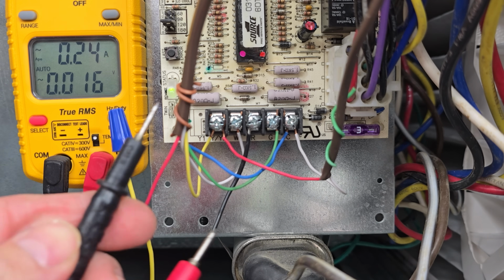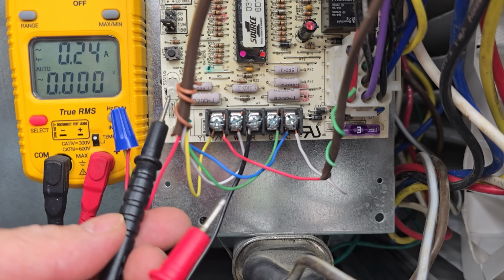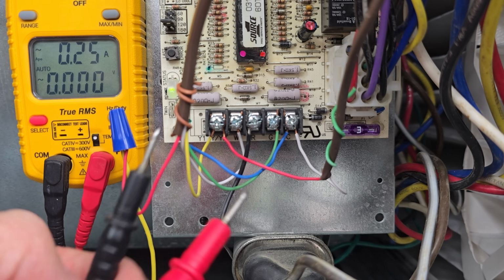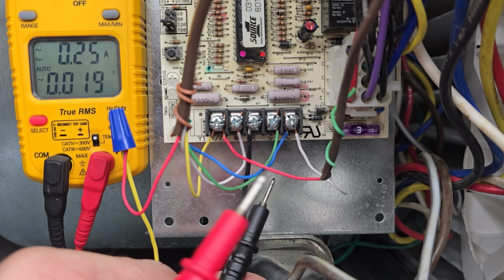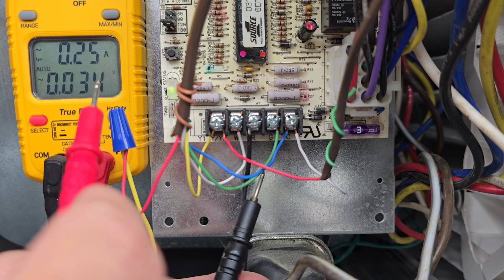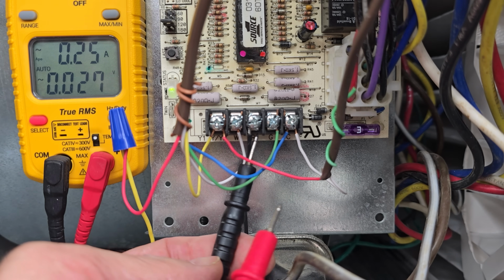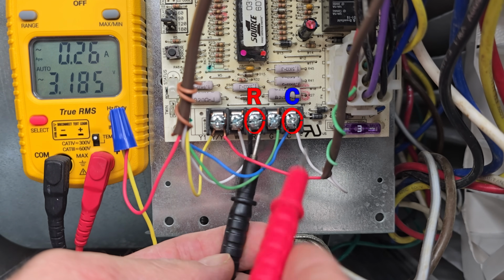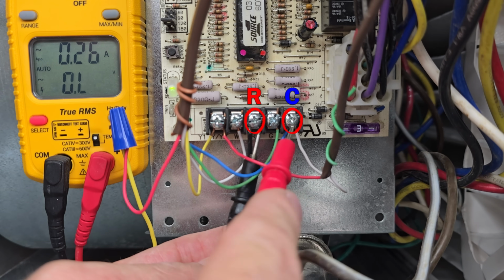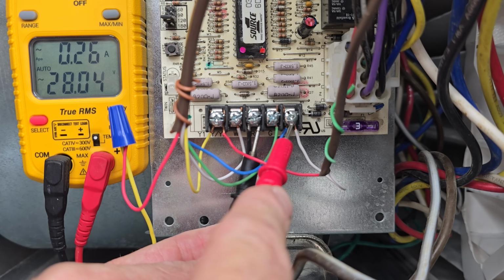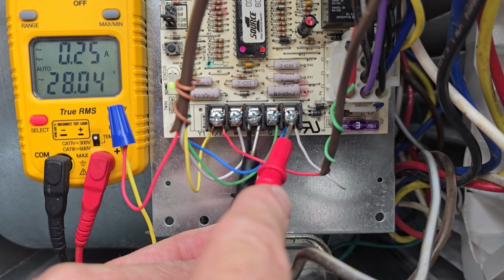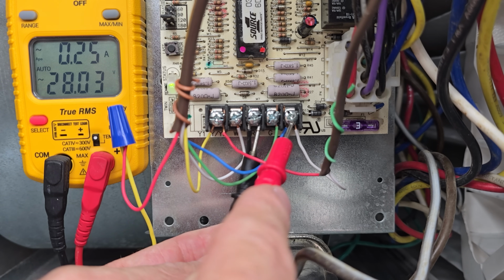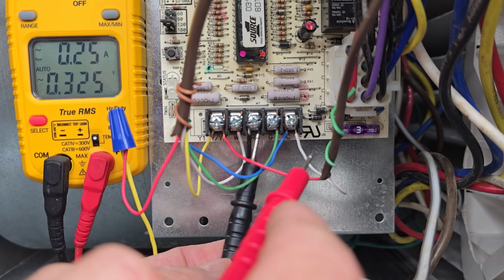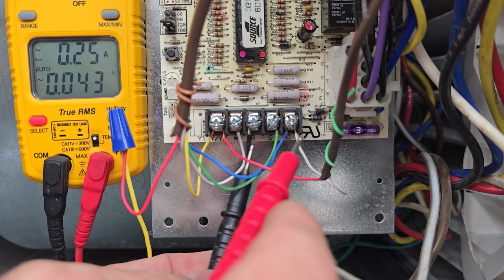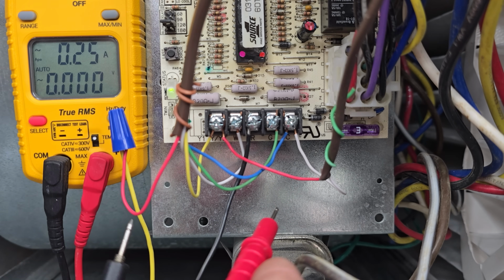We're back down in the blower compartment, and you can see the LED status code light is blinking like normal. That's because our door switch is shut, and we reset the multimeter to measure voltage for alternating current. And so we're going to put one probe on the R terminal and one on the C terminal. And so we're measuring for 24 volts, so that's anywhere between 24 to 29.5 volts, and we're measuring 28 volts. So you can tell that this wire right here, your red wire, somewhere between here and the thermostat, that wire is broken. And I'm going to get to that in a second.